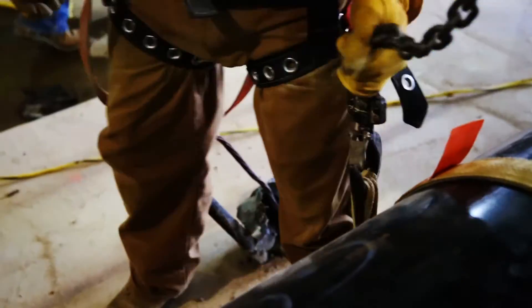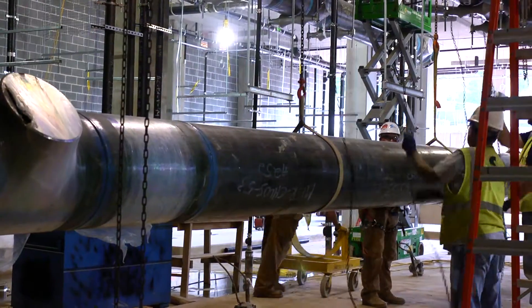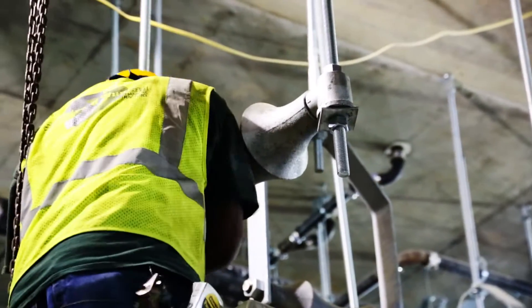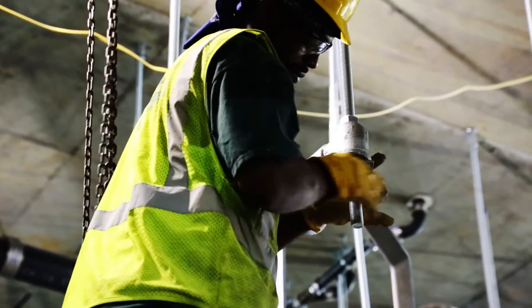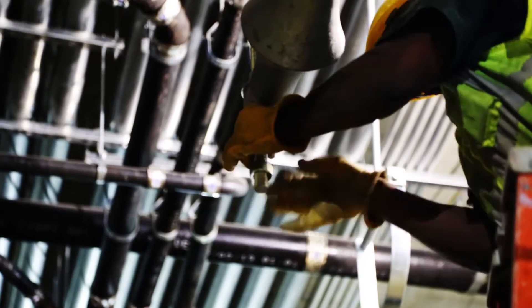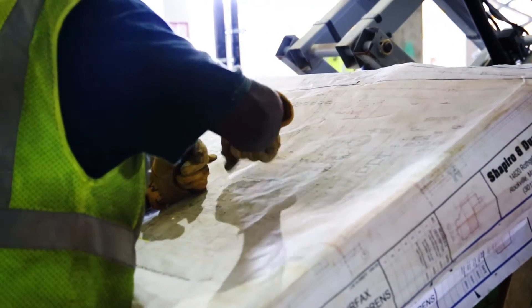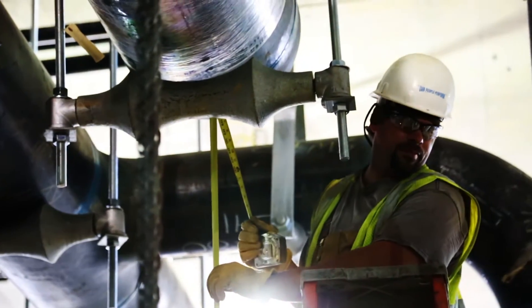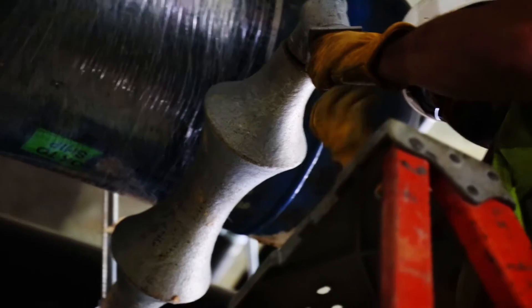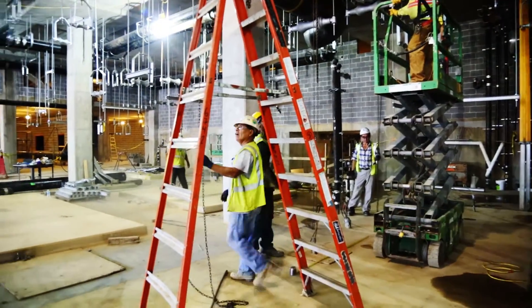The straps are then connected to the chains. Four men simultaneously work the pulleys to lift the pipe into place inside the hangers. These hangers will not only hold the pipe in place while it's bolted and welded to the other spools in the system, but also serve as a means for the pipe to expand and contract when the temperature changes in the system. This flexibility causes much less stress on the system and increases its life and functionality. When the pipe reaches the proper height, workers bolt the hangers into place, holding the pipe while the system is assembled.